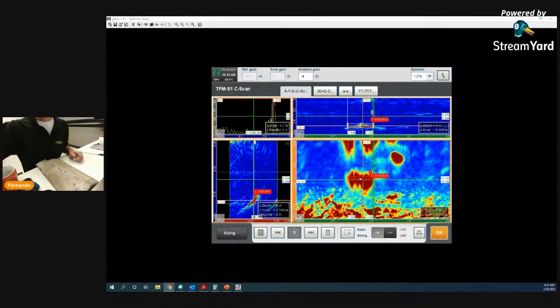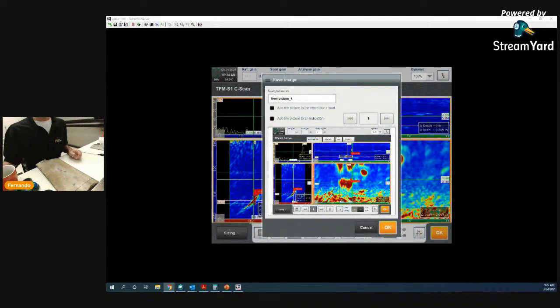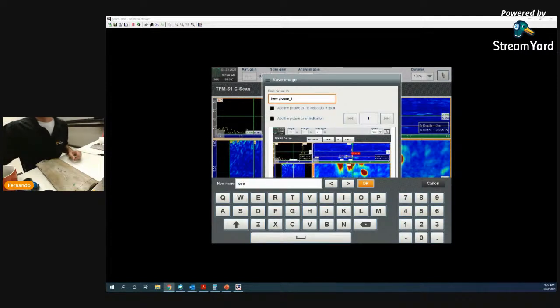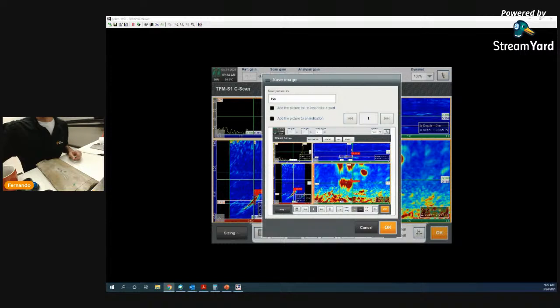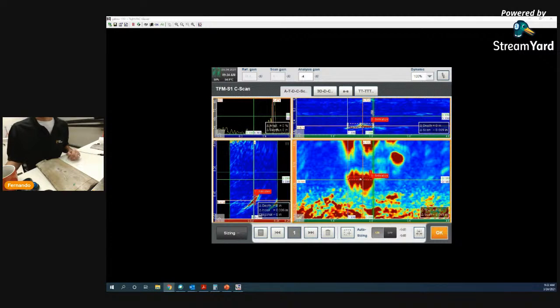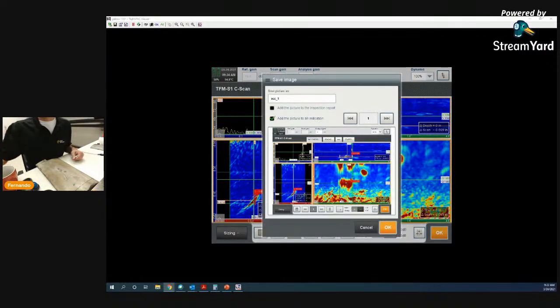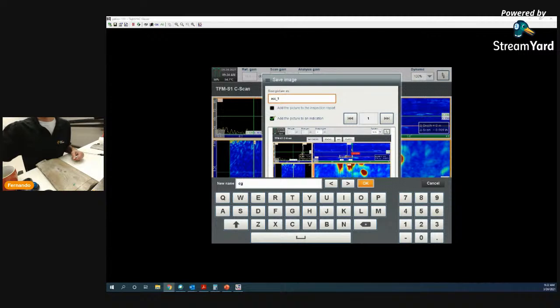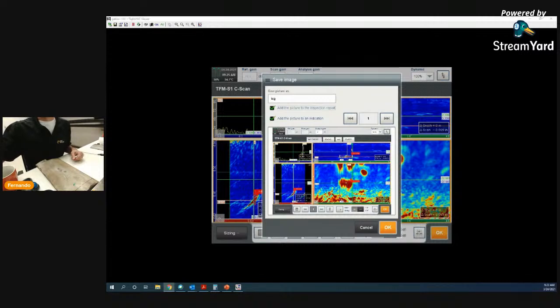The other thing we can do is take a screenshot no matter where you're at. You can take a screenshot and say I want to do SCC. I hit OK, add an indication to indication number 1, hit OK, and it adds it to that indication. The other thing I can do, if I'm doing a dead element check, wedge delay calibration, or TCG, and I want to put that into the report, is take the screenshot wherever I'm at. I can take the screenshot and say this was a TCG. I hit OK, add the picture to the report, and hit OK.